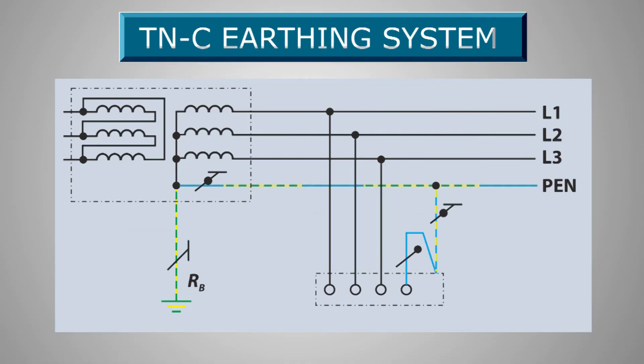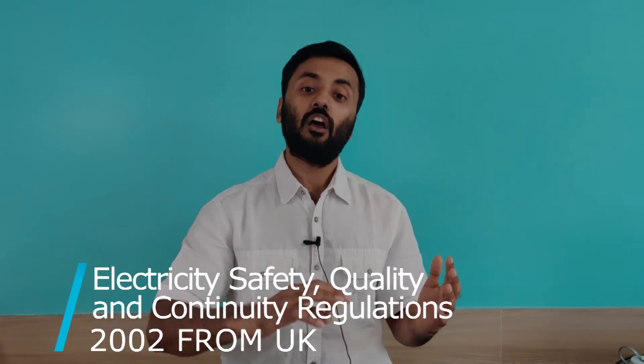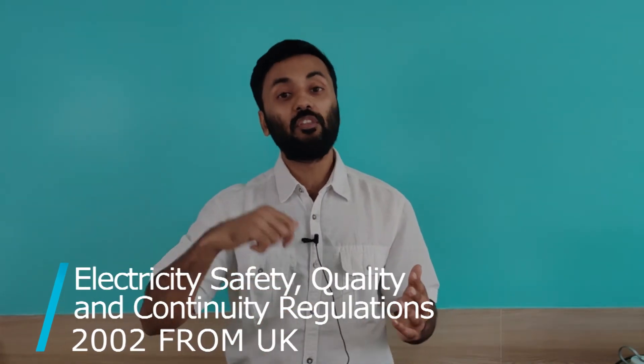The TNC earthing system: the neutral and protective earth are combined into a single conductor throughout the system. All the exposed and conductive parts of the installation are connected to the PEN conductor. As per Section 8-4 of the Electrical Safety Quality and Continuity Regulations from 2002 from the UK, a consumer shall not combine the neutral and protective functions in a single conductor in his customer's installation.